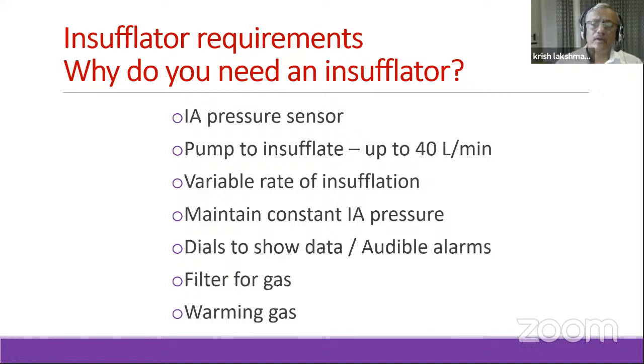So you need insufflators that have a maximum of 20 liters per minute, but there are some with 40 liters per minute as well. You need that kind of good pumping that's required. It must be a variable rate depending on the intra-abdominal pressure. And it's important that you have alarms and some dials to show you what's happening.